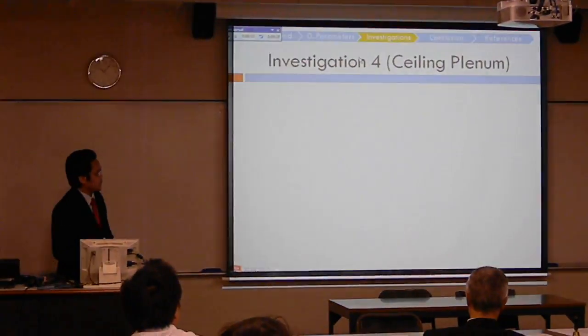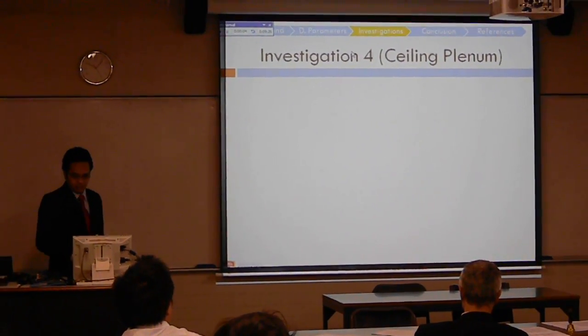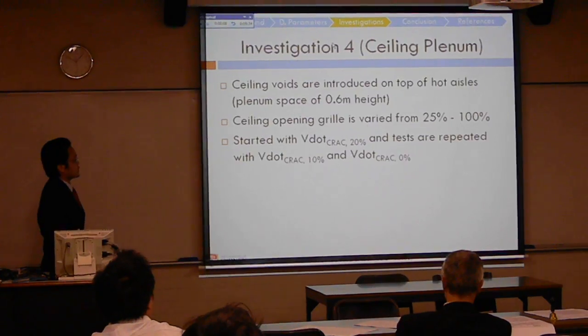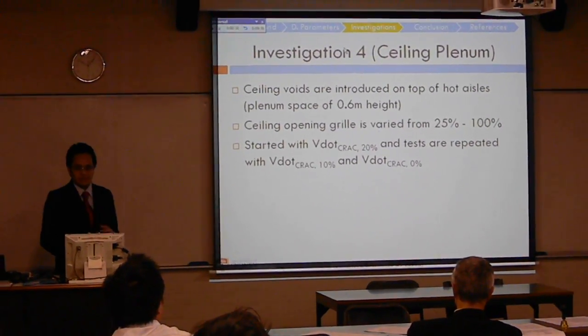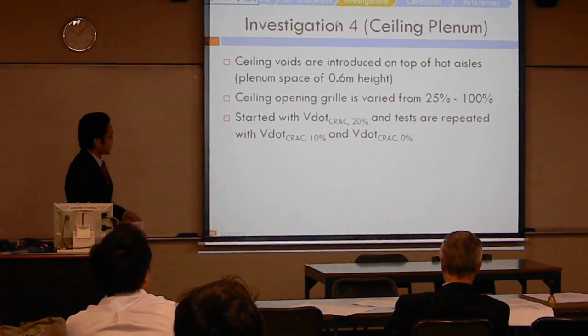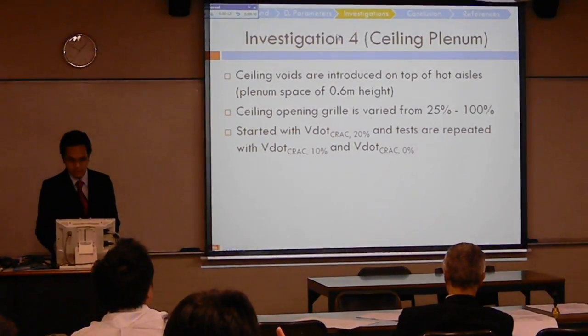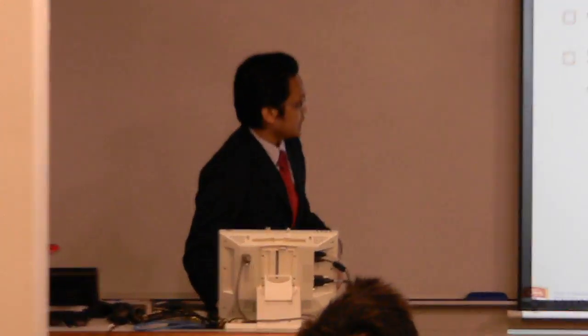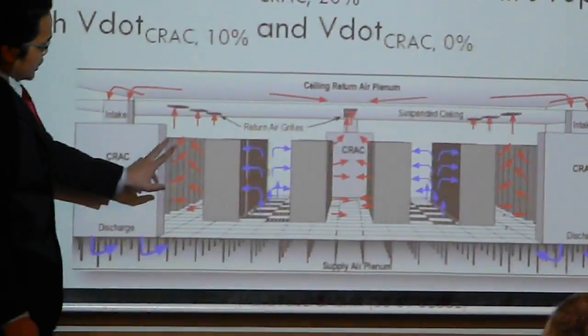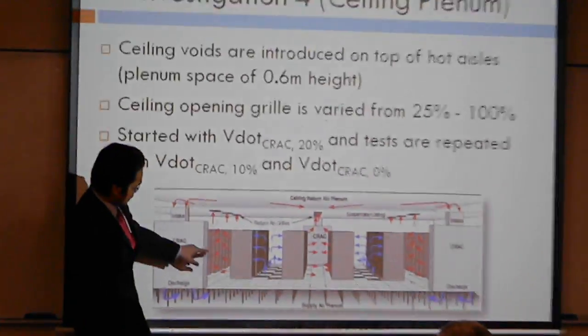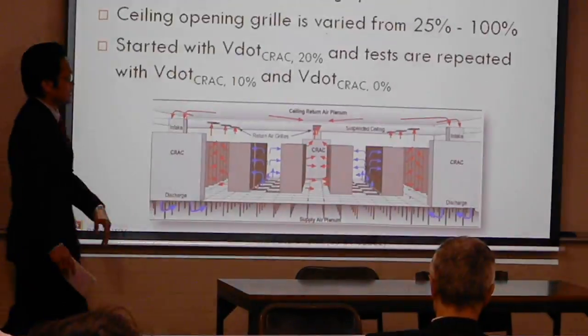Investigation 4 is all about the construction of ceiling vents. The ceiling vents are introduced on top of the hot aisle with the opening ratio ranging from 25% to 100%. Similarly, I started with CRAC units at 20% extra airflow and repeated that with 10% and 0% extra. This is the illustration — we have the data center with the ceiling, so hot air can easily get up on top, straight above the hot aisle.